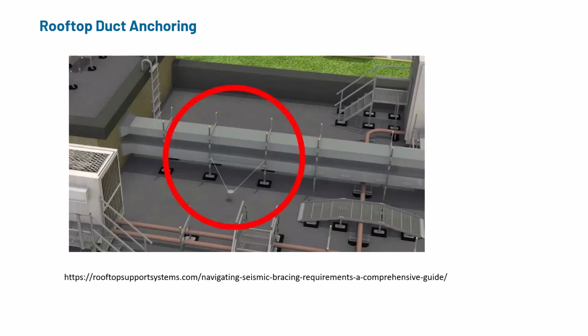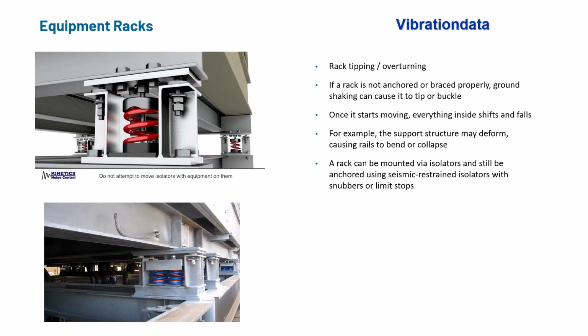Fun stuff. So here is rooftop duct anchoring, and anchoring is used to limit the displacement of that duct, and is a very prudent idea. So here we've got some equipment racks, and they're mounted on different types of springs. The bottom arrangement's called a tandem spring, and this will lower the mounted natural frequency of the equipment and help mitigate the effects of the transmitted vibration due to base excitation.